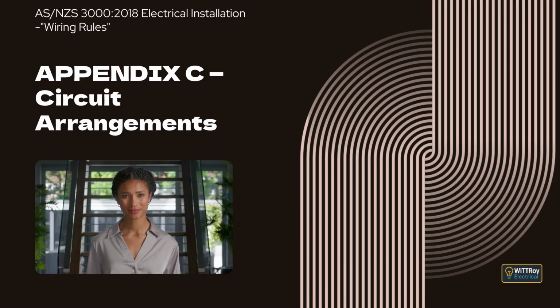Clause C2.5.2.3 Resistance welding machines. This clause explains how maximum demand is determined for resistance welding machines. For individual machines, the demand depends on whether the operation is varying or specific. Where duty cycle is known, a multiplier is applied to the actual primary current. For groups of machines, the largest machine is taken at full assessed value, with reduced values applied to the remaining machines.